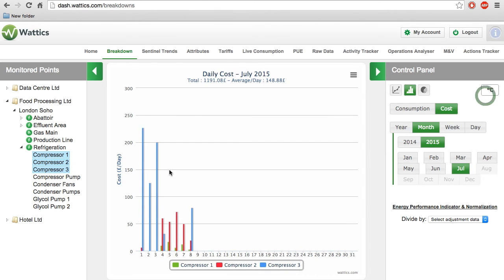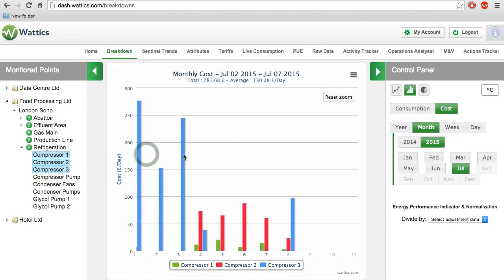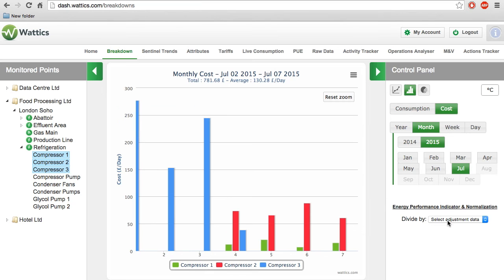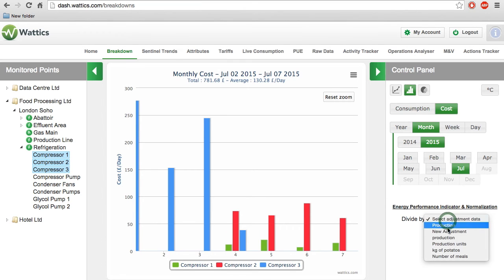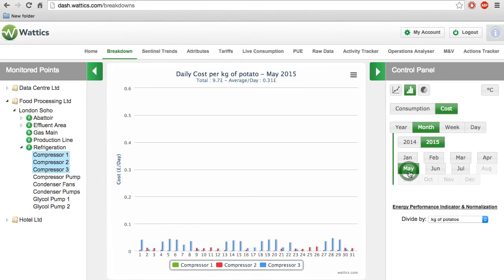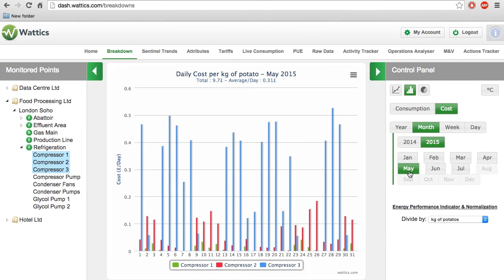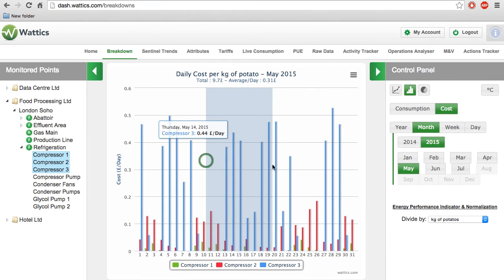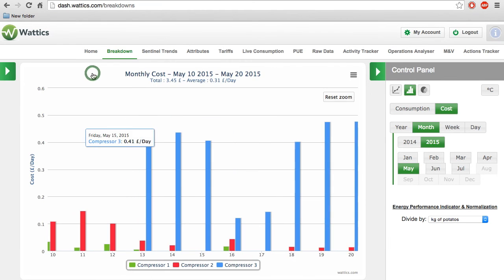Another useful tool is to normalize the consumption by energy performance indicators such as production or kilograms of food processed. If production or sales are increased, then adjusting the data in terms of consumption per tons of food processed will make sense of the associated increase in energy consumption.